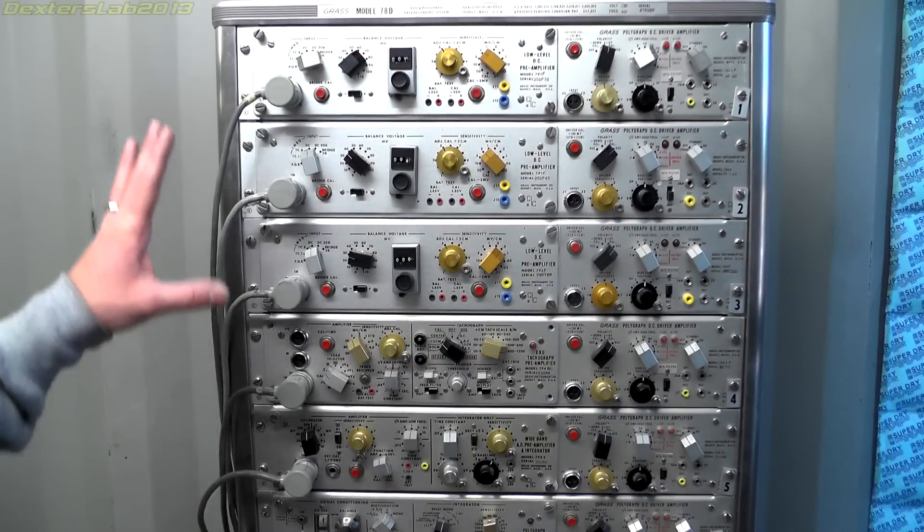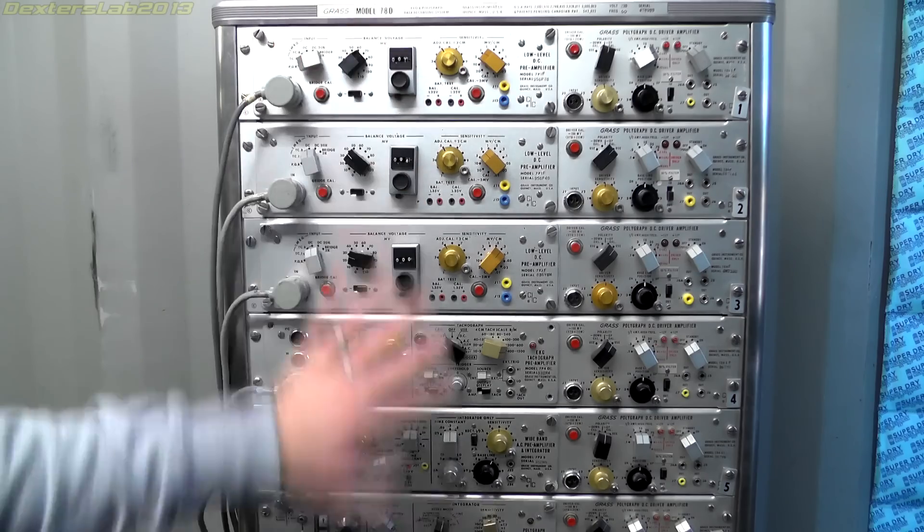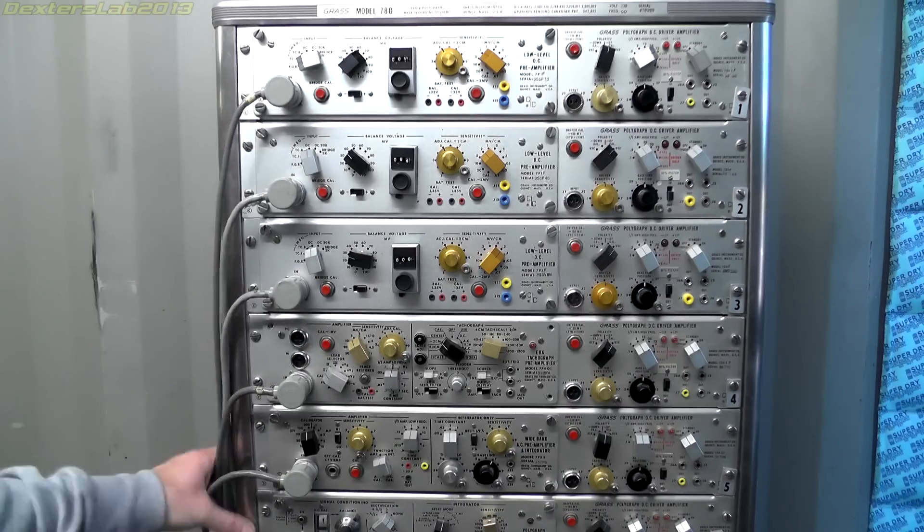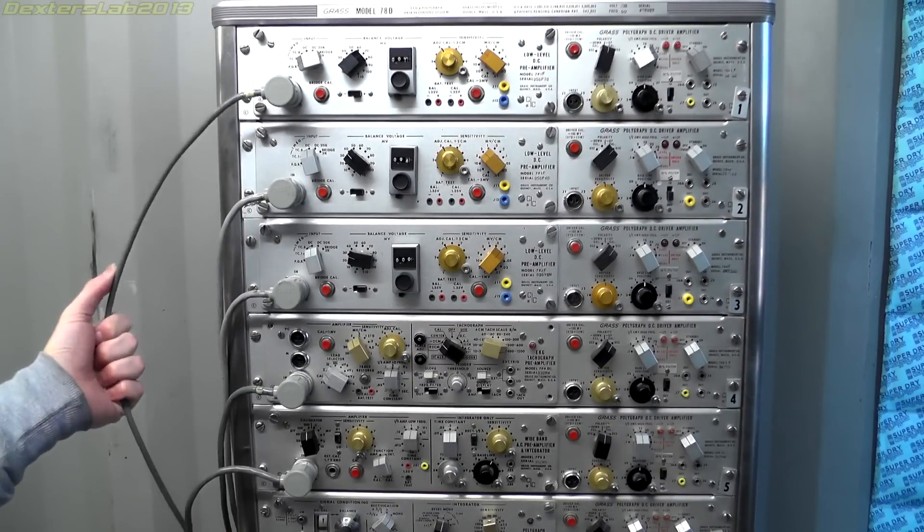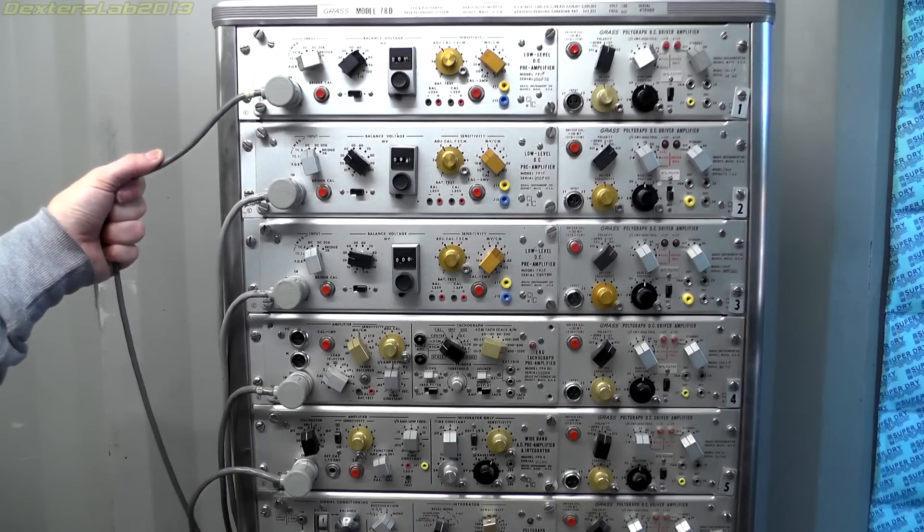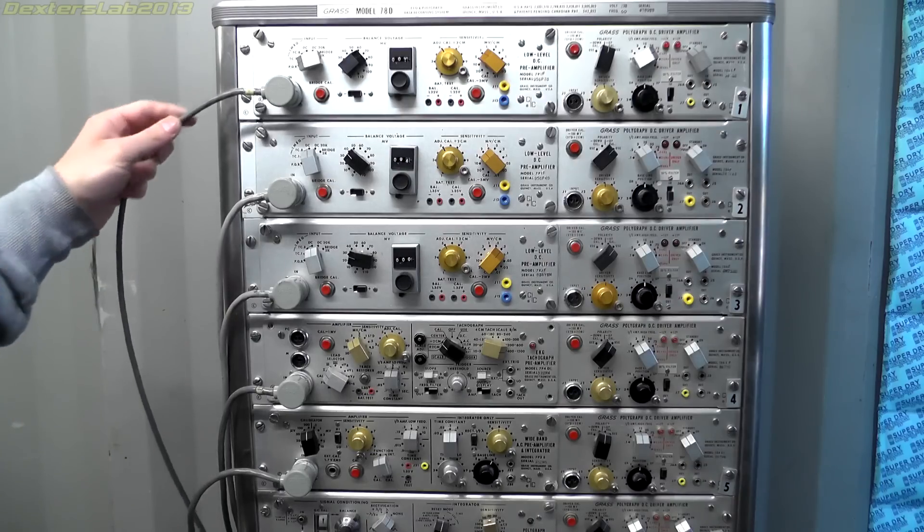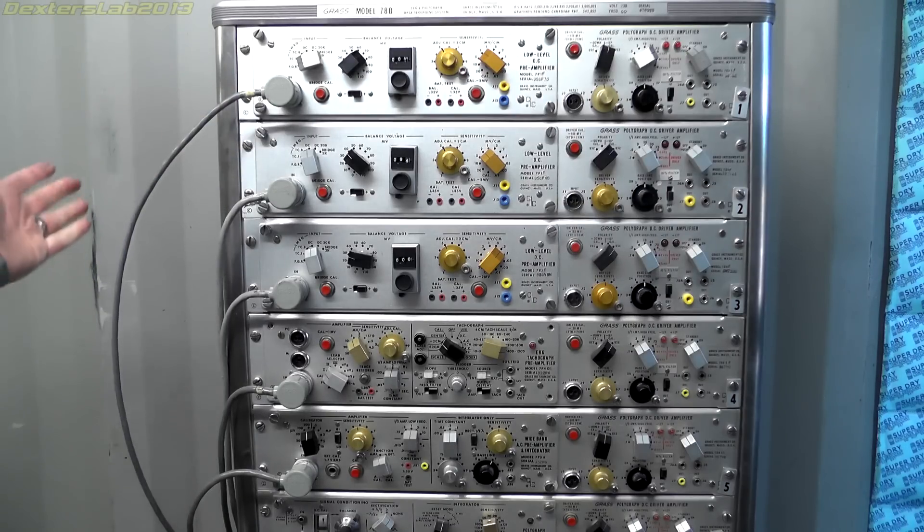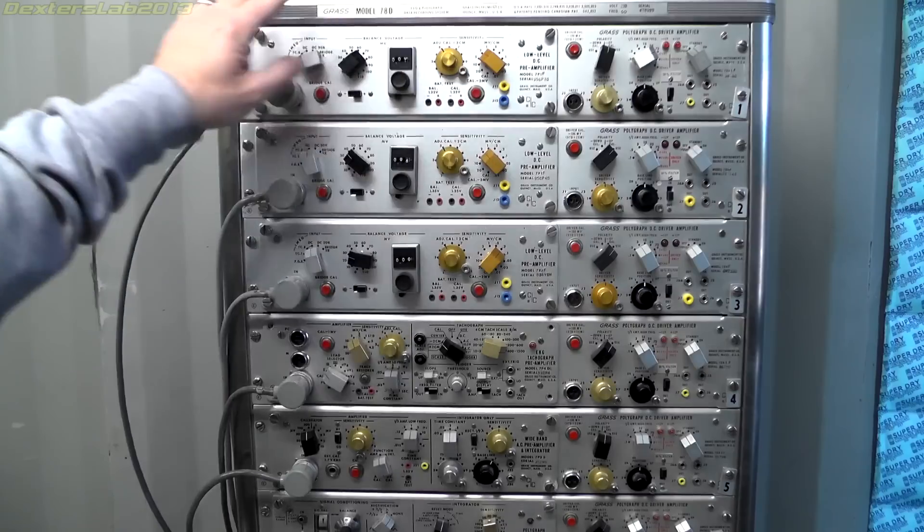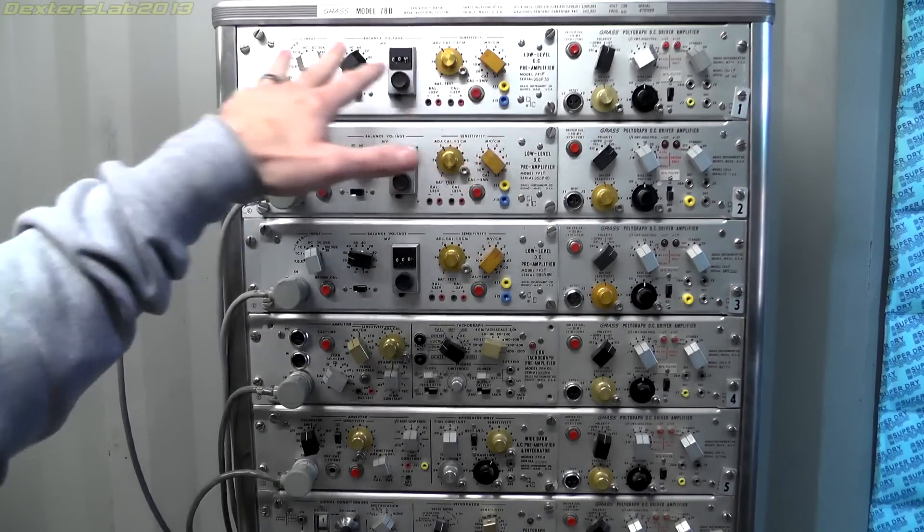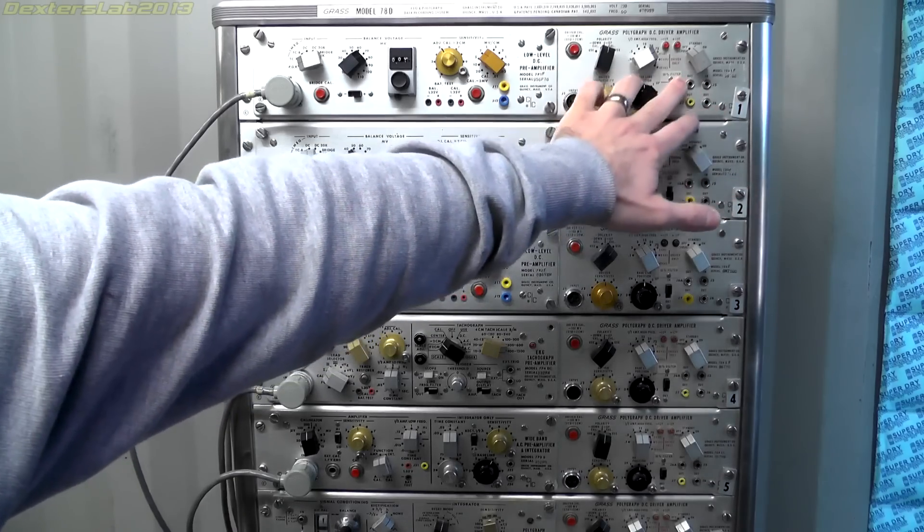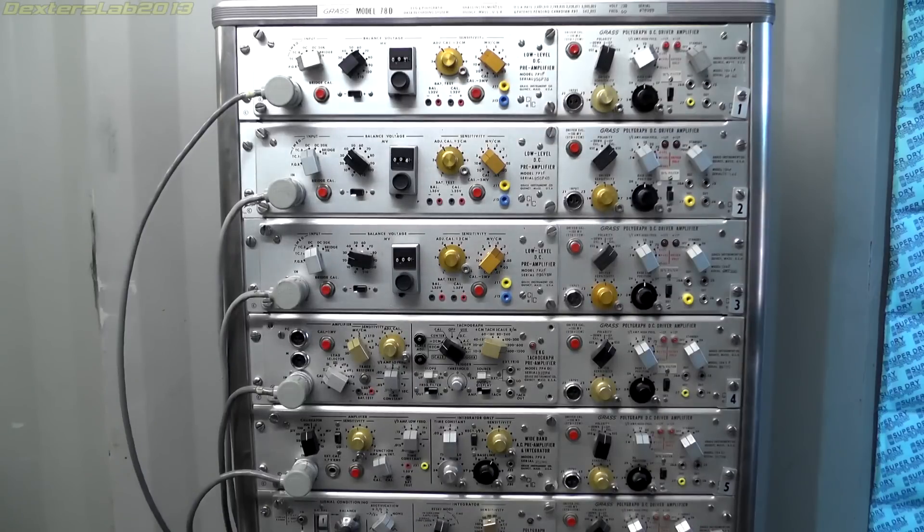OK if we head back round to the front here I'll just run through the various things that I've managed to infer from looking and playing around with this. What we have at this section here seems to be all the actual inputs. So each input which comes from the patch panel that you saw earlier would connect to all the different probes and sensors that would be attached to the device under test or the human. Those would be very varied. There would be lots of them. So the analogue signal comes into this unit here. This is a low level DC preamp. We have three of these on this particular machine.